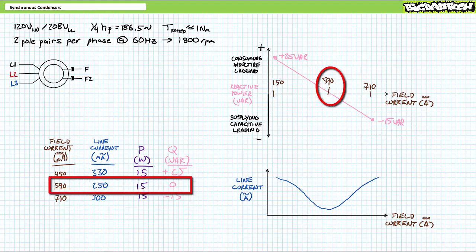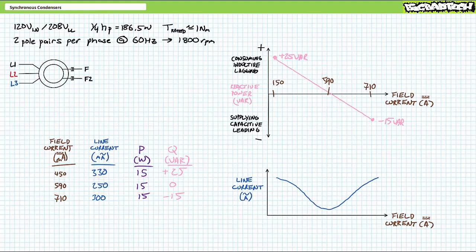When we dial field excitation current back down to 590 mA DC, the synchronous condenser draws 250 mA line current per phase, perfectly in phase with supply voltage, and neither draws nor supplies reactive power. Each winding consumes only 15 watts of real power to overcome friction and zero VARs of reactive power. This confirms the theoretical plots of reactive power as a function of field current and line current as a function of field current for electrically excited synchronous motors — the only difference being the synchronous condenser is mechanically unloaded.